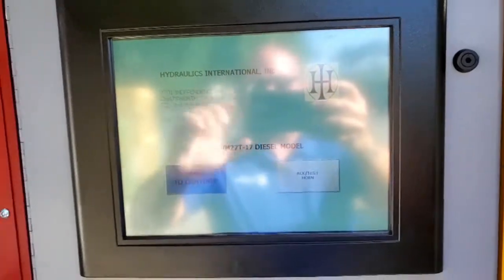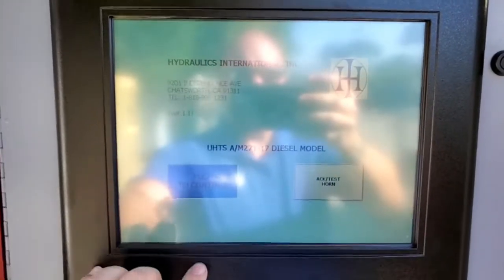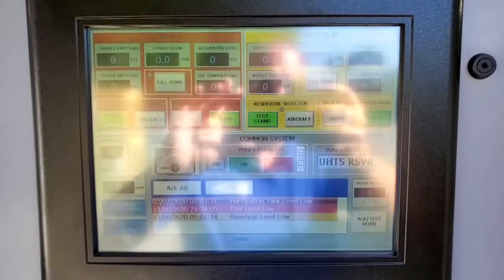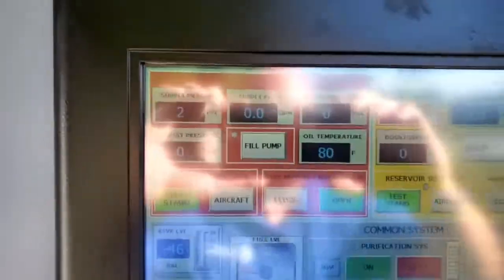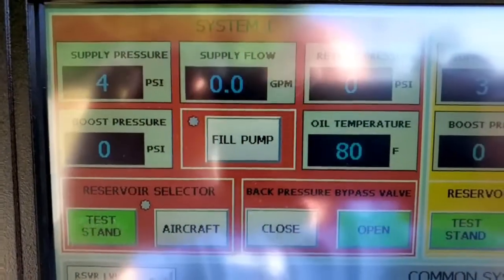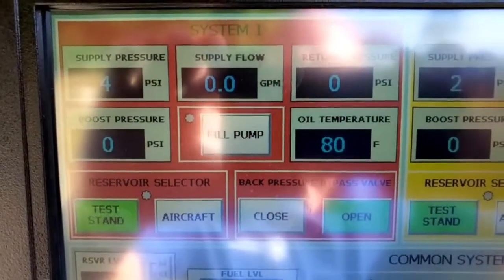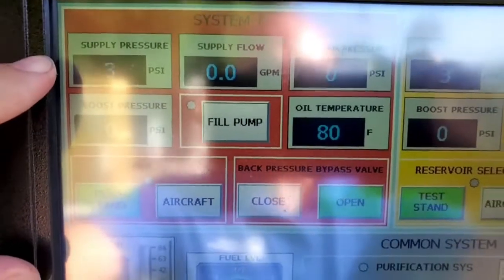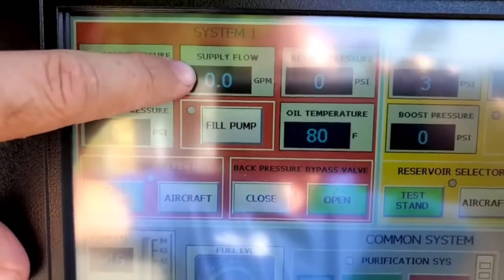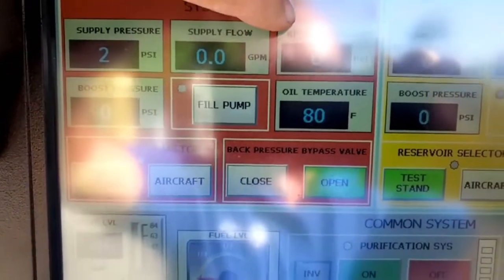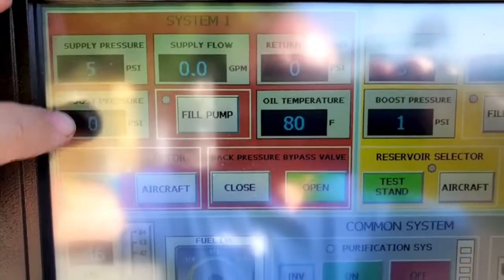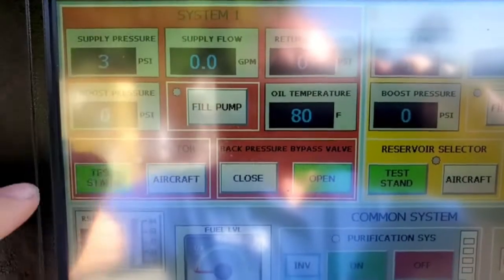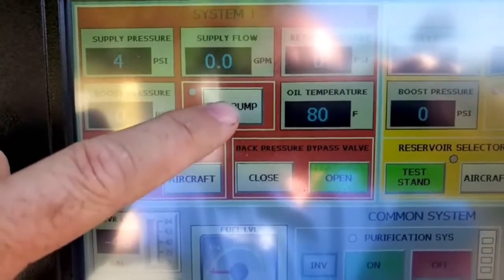Now that our HMI is fully booted up, we're going to press the push to continue button to proceed to the home screen. Okay, you're on the home screen. You have system 1 information. You have supply pressure, flow in gallons per minute, return back pressure, boost pressure, oil temperature. You can operate your fill pump by pressing this button.